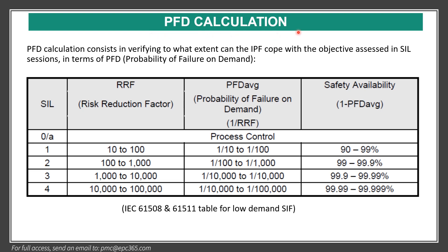For PFD calculation — for example, for SIL 1 — the probability of failure on demand based on IEC is 1 over the risk reduction factor, which is 1/10 to 1/100. Risk reduction factor is between 10 and 100. Availability is 1 minus PFDavg. For example, if you write it in performance standards, the availability of this loop should be 99%. This is the IEC 61508 and 61511 table for low demand SIFs.